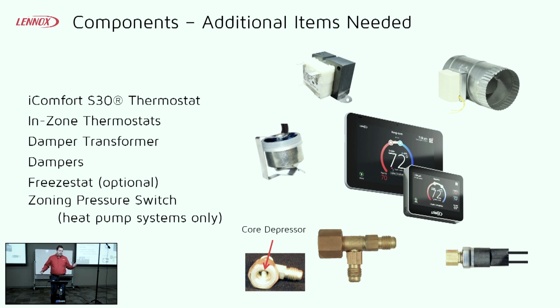Your main components, the S30 is always going to be zone 1 on these systems. For zones 2, 3, and 4, you need an additional in-zone thermostat. You need a separate damper transformer to run your dampers, run your damper control module. Of course, your dampers, your Freezestat, which is an optional component that can be useful in these circumstances, especially on maybe a 2-stage system, or if you're using a single-stage application, it can be very important to use. And then the heat pump pressure switch.